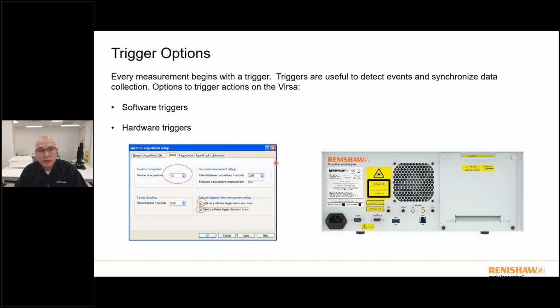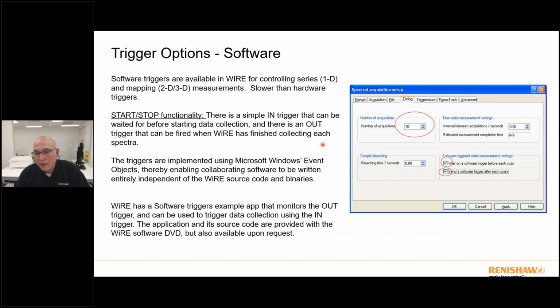We also have options for triggering, and triggering can be useful for synchronizing data acquisition with different events. There are two different ways of doing triggers with the Renishaw system, either through software or through hardware. And I'm just going to briefly describe both. Software triggers are designed really with start-stop functionality. It is just monitoring the Windows event log, so it really just gives users the ability to program, independent of the Renishaw system completely, some way to synchronize and initiate or end experiments using the Renishaw system.